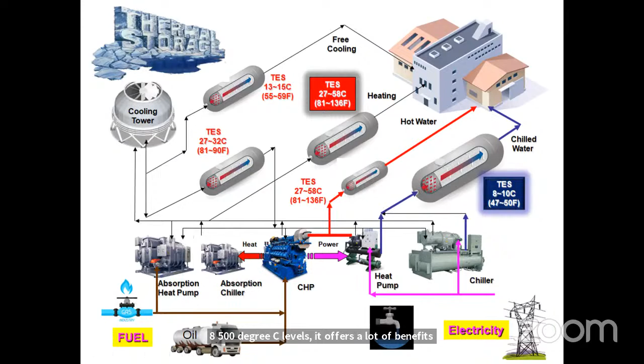The conclusion is that thermal storage, including ice at different temperatures from 0 degrees C, lets us utilize free energy. What's free? The cold night and the warm day. If we bring the warmth of the day into the night, we reduce heating; if we bring the cold of night into the day, we reduce cooling demand. Getting it totally free would be great, but nothing in life is entirely free—we have to use, waste, and spend something. When using machinery like heat pumps, always look for ways to minimize waste. If we're producing cold, we're dumping heat somewhere, and vice versa—if we're producing heat, we're extracting energy to make cold. So the question is: can we use that?